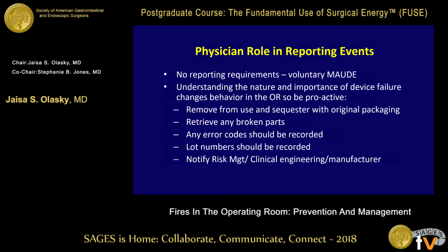In addition, you should, of course, remove whatever's not functioning from the OR, sequester it with the original packaging so that you have lot numbers, retrieve any broken parts. Error codes, if it's an electronic device, should be recorded as well, lot numbers, and notify risk management, clinical engineering, and the manufacturer of any equipment that's not working properly.